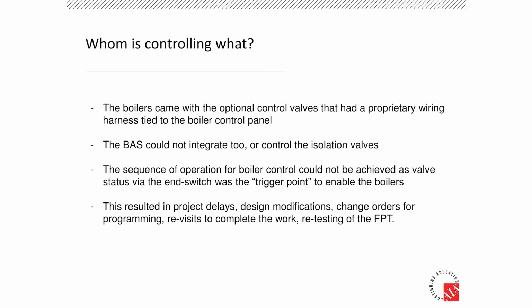So then I read the control submittal and say, well, they're controlling the isolator valves. And there was some sequencing for the building automation side of the house on how to enable the boilers based on isolation valve position. We get out onto the site, and what we found is that the boilers did come with their own valves, and they had a proprietary wiring harness tied back to their boiler control panel. The boiler control valves and their positions and statuses were not points that could be integrated back to the building automation system. The building automation system was trying to fire boilers when the valves were closed.